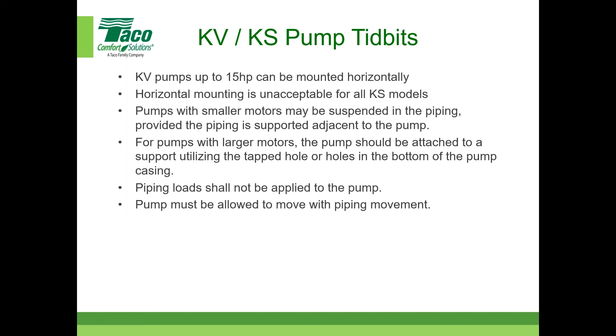Piping loads are so important. This is important for all pumps: piping loads shall not be applied to the pump. The pump has to not take any of the loads from the piping. So that piping has to be designed properly with the proper pipe hangers all around. It needs to be allowed to move with the piping, so the stand can't be hard bolted down. Don't rigidly connect it to the floor. And I can't emphasize this enough for any pump installation.